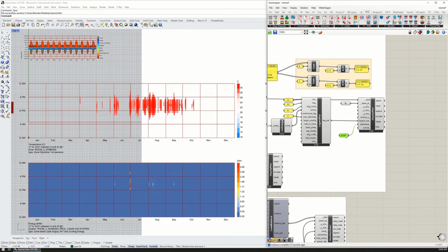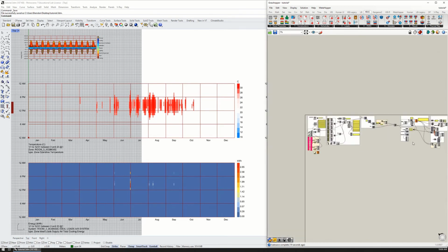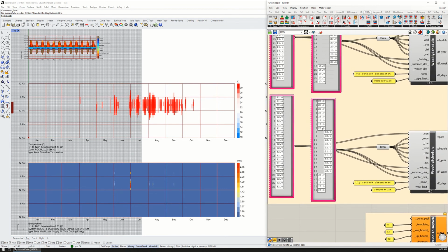This is pretty warm. And so then I went and checked out my set point again, and I realized that I reversed these two. So I have a 28 degrees Celsius setback and a 32 degrees Celsius thermostat. They should be the opposite of that. So I'm going to pause the video and reset this, and we'll see the difference that makes.